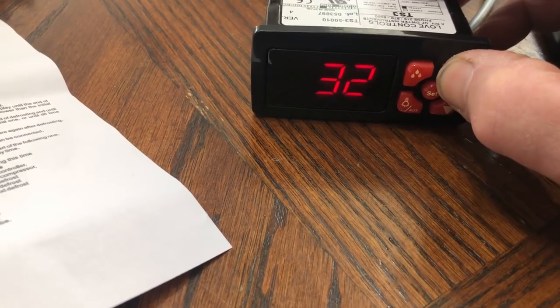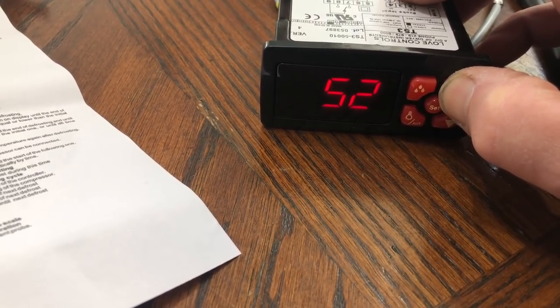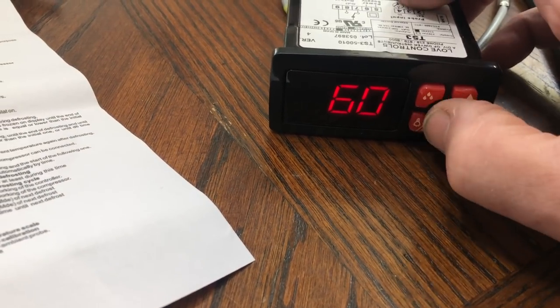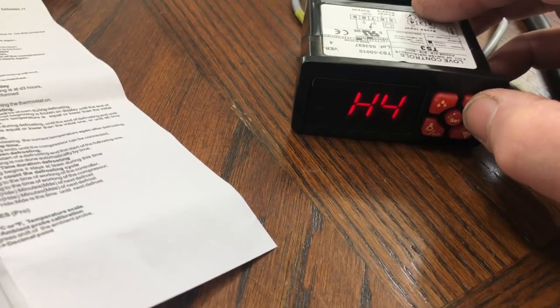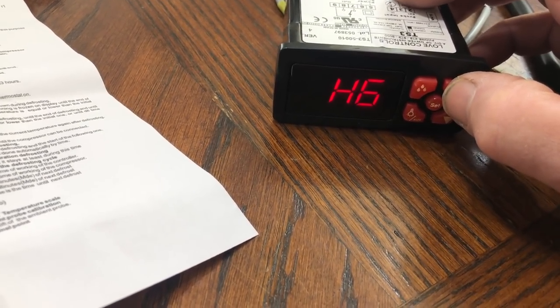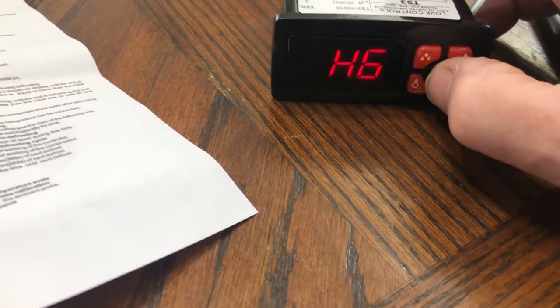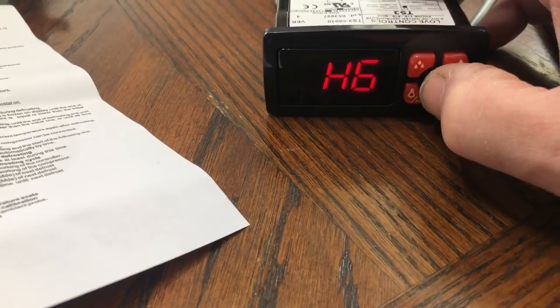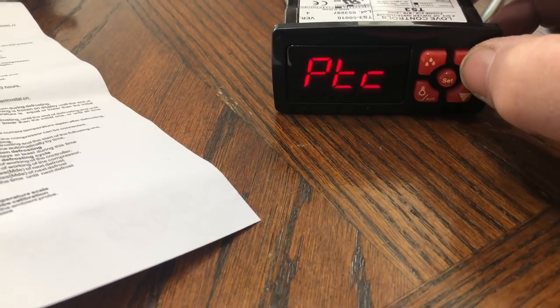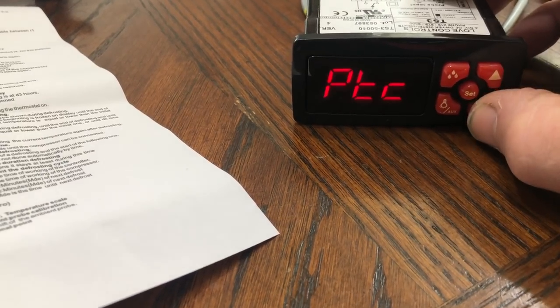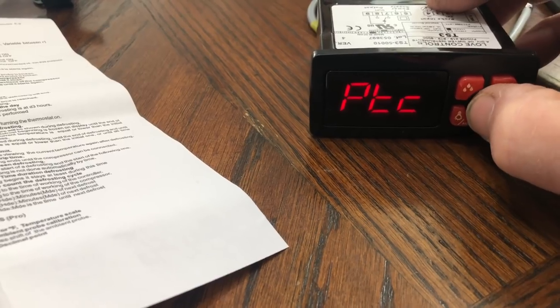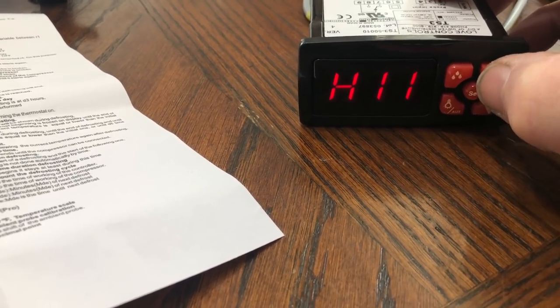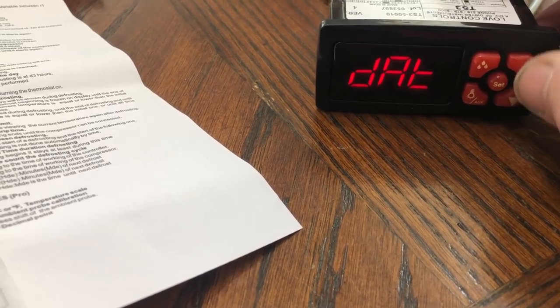And we'll go H4. Address and serial communications. H5. Keypad code. H6. Type a probe. That's an important one. Depending on... If you have a failed probe out there, you could use either type of probe. So you can go between the PTC or the NTC. I got it set for the PTC. H6 set, PTC. And then H11 gets into some other stuff. And then you get into some dates. Things like that.